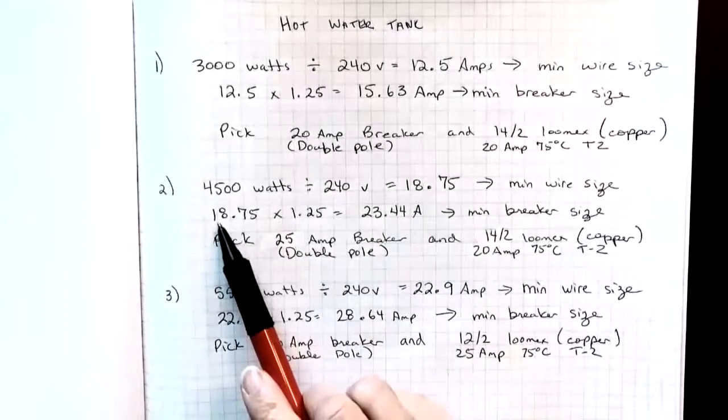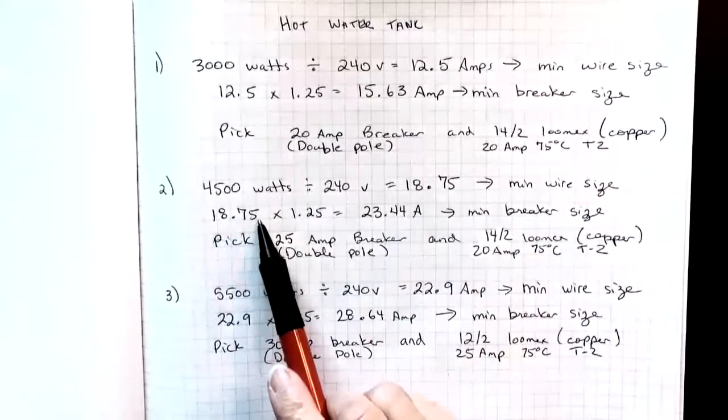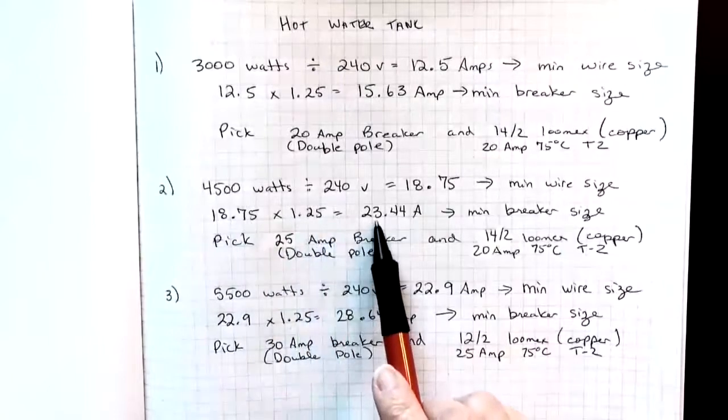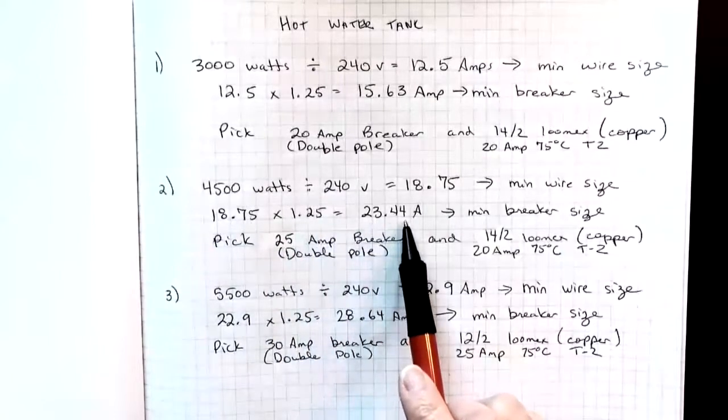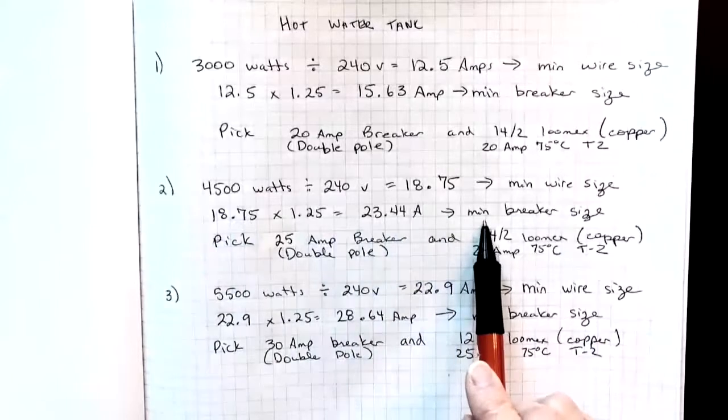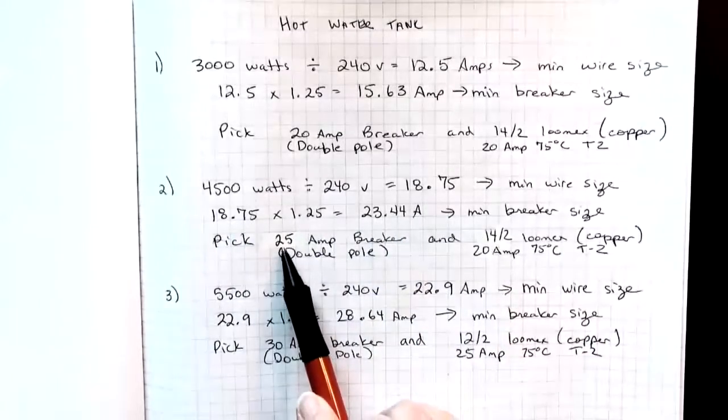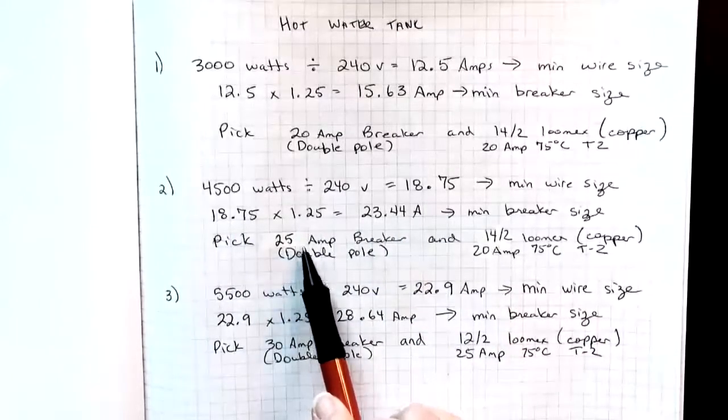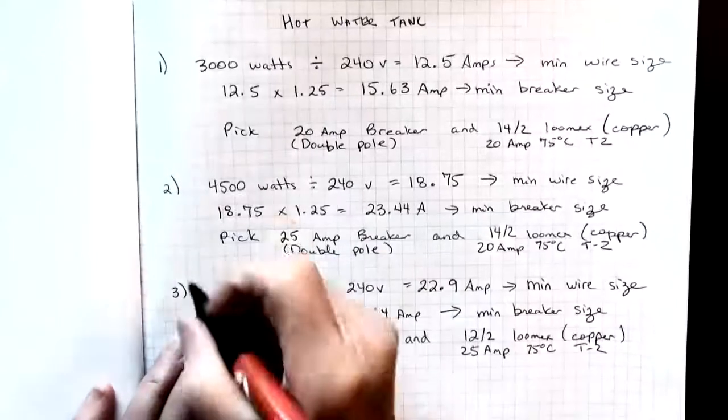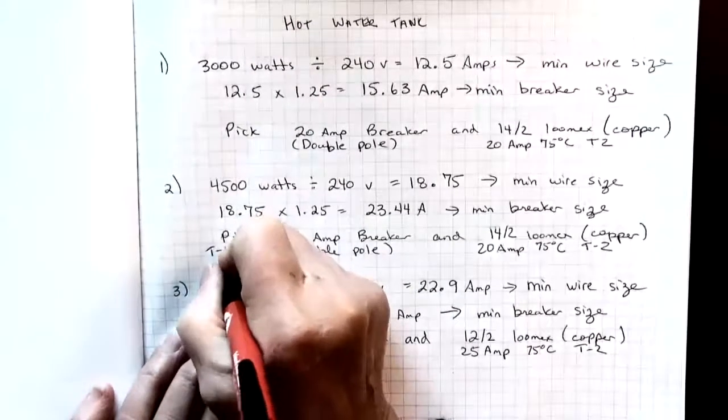Then to find the breaker I take the 18.75 times 125 percent gives me a 23.44 amp minimum breaker size. So I picked a 25 amp breaker. This comes from table 13 by the way.